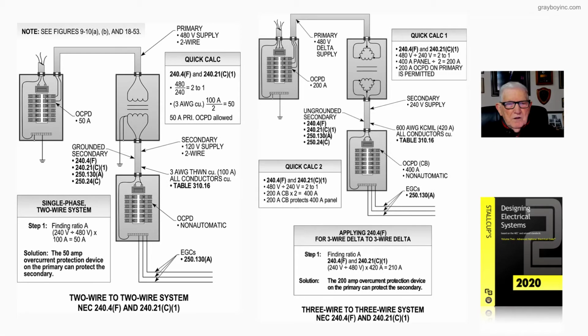Now this figure 20-9 deals with determining the full load current rating of a transformer based upon its voltage and the size of the transformer and so forth. Now, notice in the call out we have the grounded secondary side of that transformer, and we refer you to 240.4F, 240.21C1, and 250.130A and 250.24C. And of course, you know that's the size of the conductors where you're tapping off the secondary side of that transformer, where your transformer secondary conductors, so to speak, there.